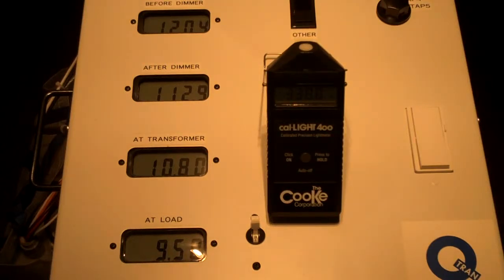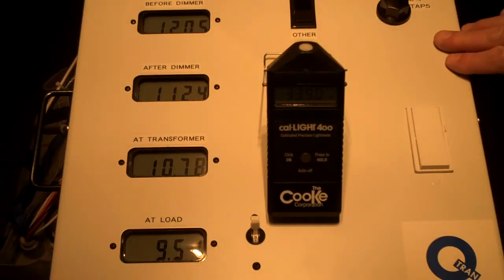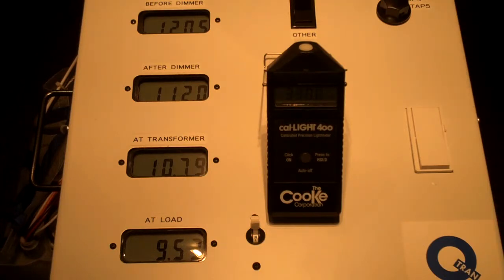This is the Q-Tran Voltage Drop demonstration kit, and this kit is designed really to show what separates our transformers or power supplies from the standard transformer that you would get from either an electrical supply house or a lighting manufacturer on a low voltage lighting system. Our transformers are toroidal, which are round in design, and toroids are known for being a quiet transformer, so we help address some noise issues.